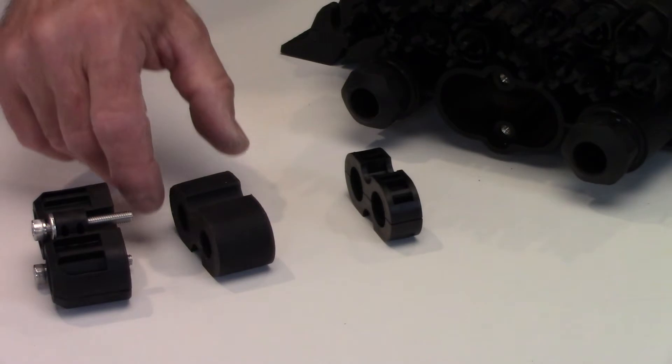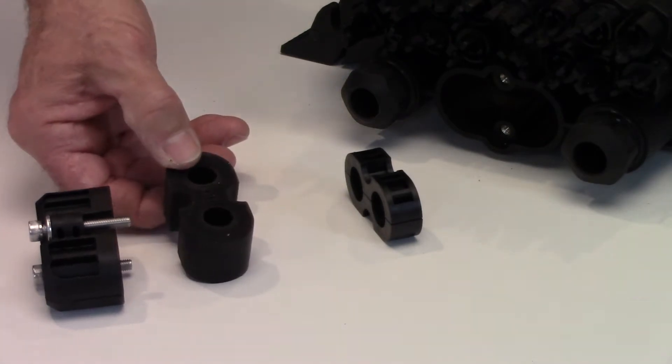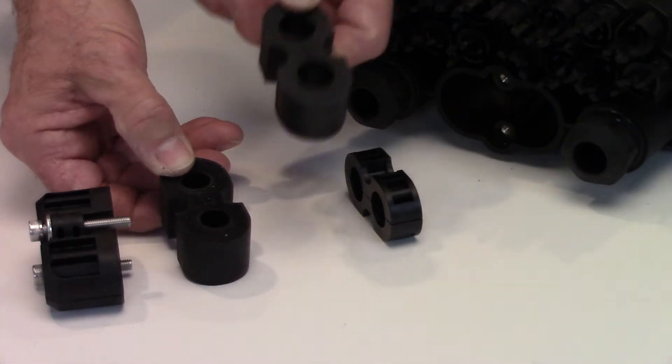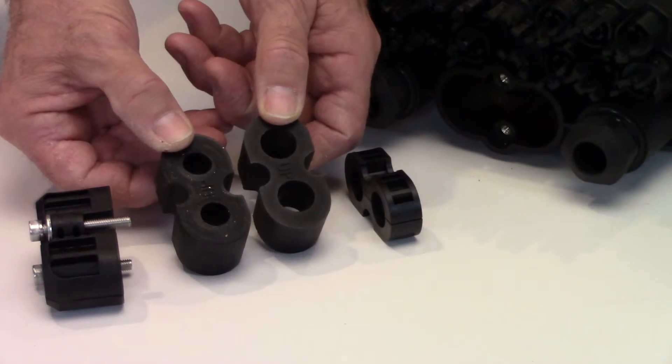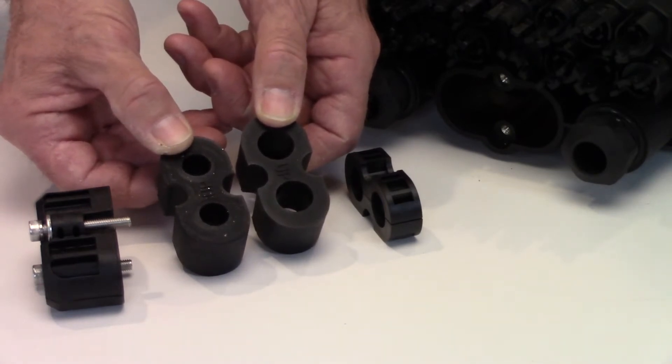The FSDC can accommodate cable diameters from 10 to 17.5 millimeters. Use the appropriate sealing grommet for the cable that is being installed.